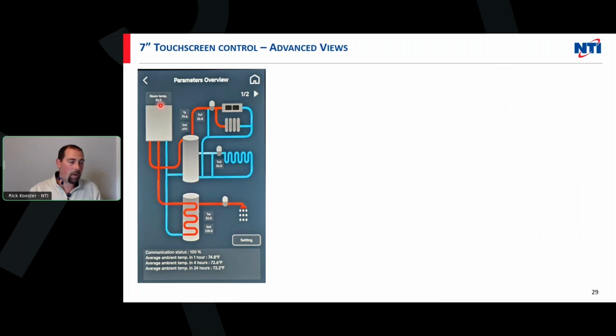In my case, this is set for Fahrenheit. If this was converted to Celsius, you'd be at 0 degrees on your sensors if they were not plugged in, so room temp would be showing 0 degrees Celsius. Mix valves: we have the ability to control mixing if we were using radiant applications and had two electronic mixing valves, we'd be able to utilize them, more specifically if you had different temperatures on a radiant. Indirect: you can see our tank temp setting, and then the actual temperature, which in this case is showing 32 degrees, which would tell me that it's not seeing it. So we're not using an indirect.